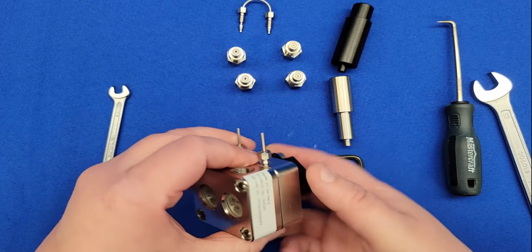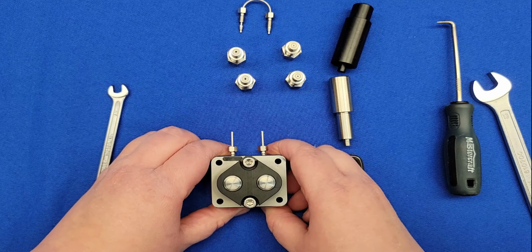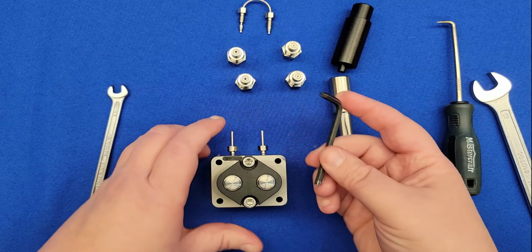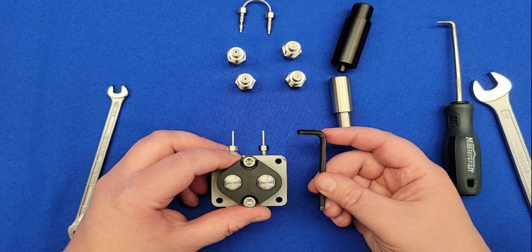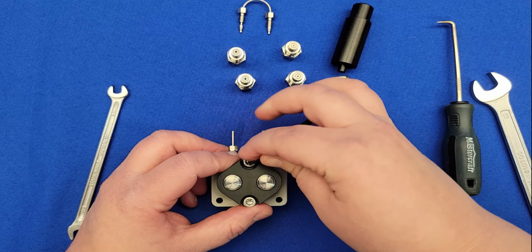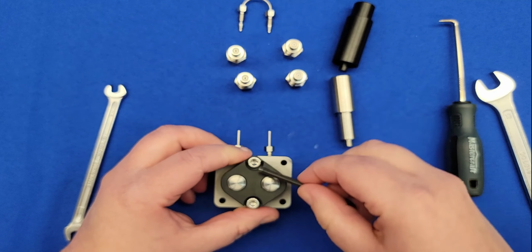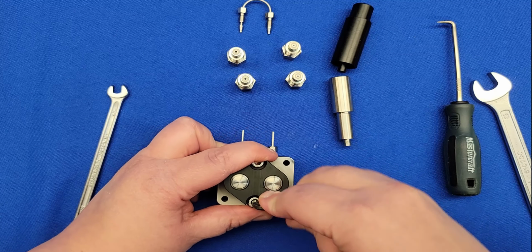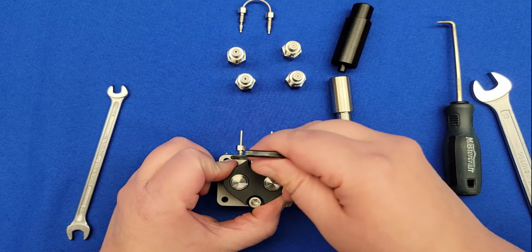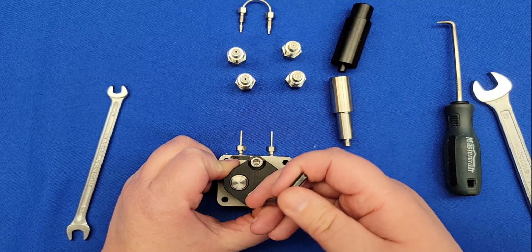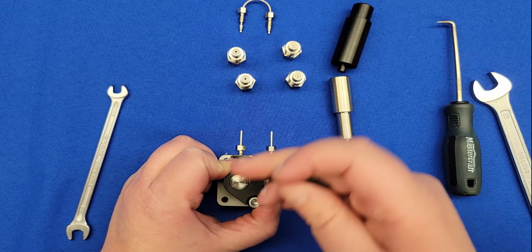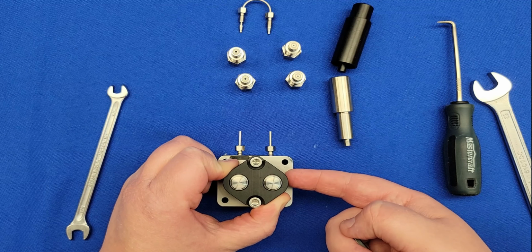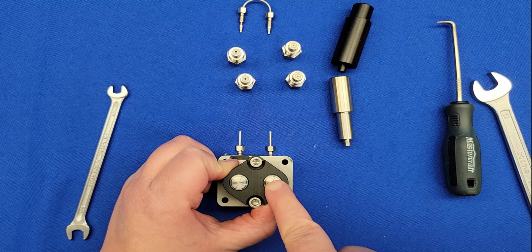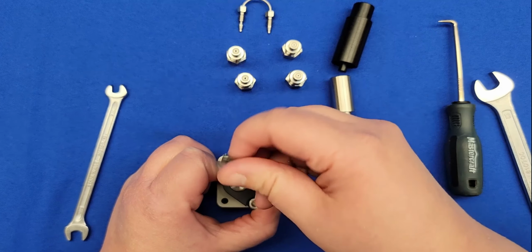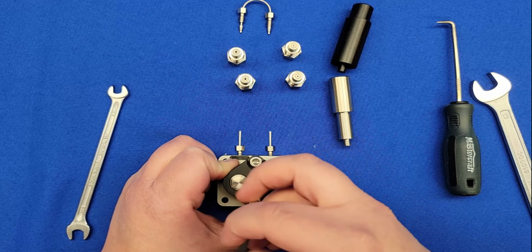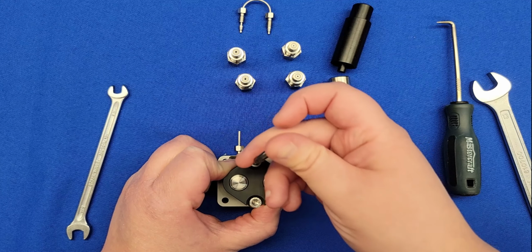Once those are removed, we move along to the other side of the pump head. Take your 4mm Allen key and start unscrewing. Make sure you unscrew a tiny bit on the top, then a tiny bit on the bottom, and move like that until it's all removed. The reason is there are springs here compressing for the piston — if we unscrew only the top or only the bottom, it can snap back and break your piston.